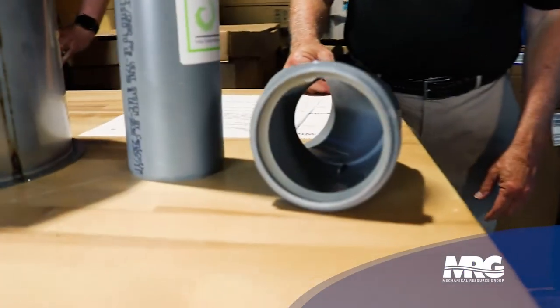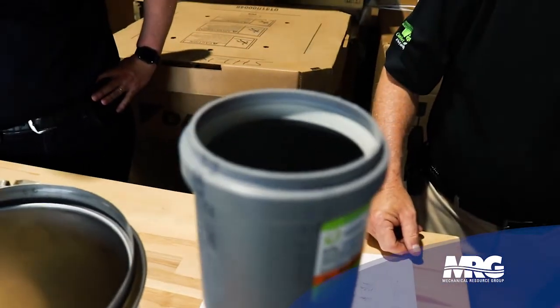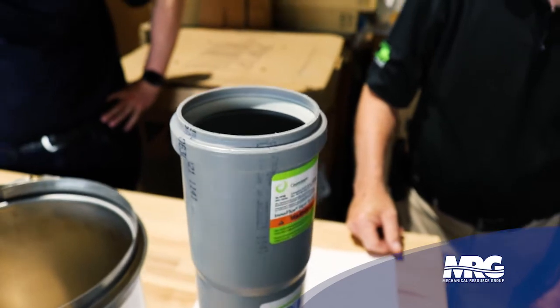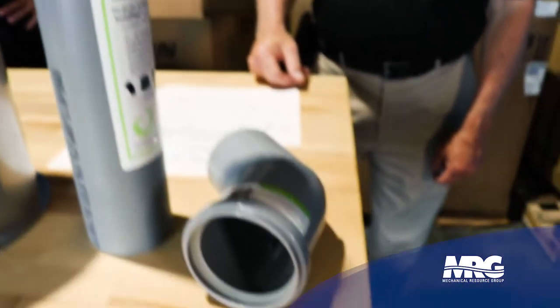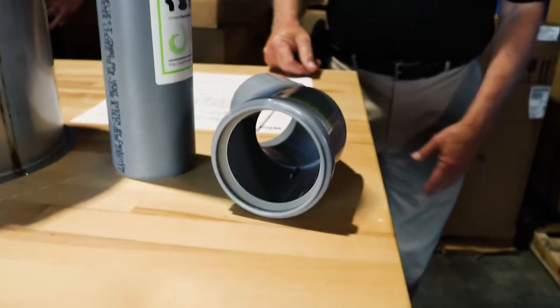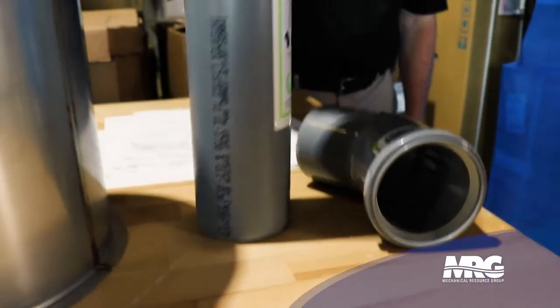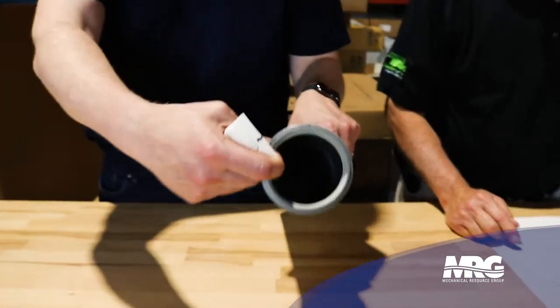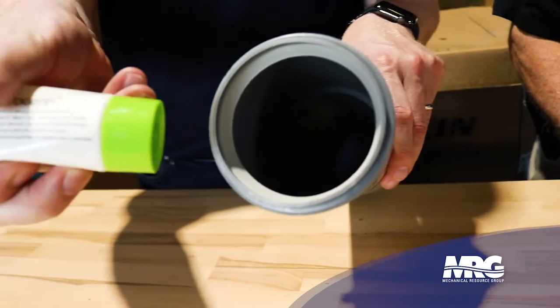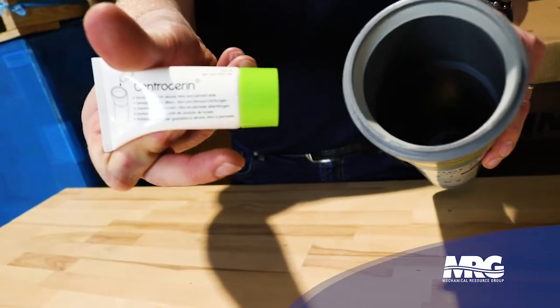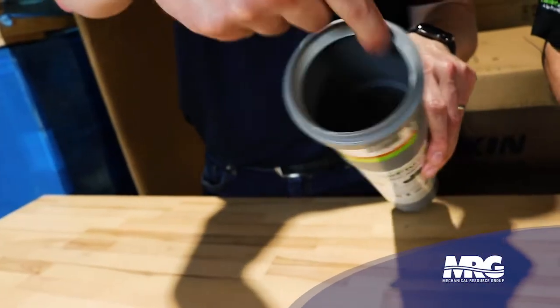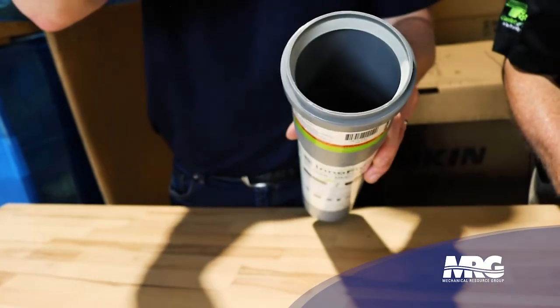We were talking about on the Category 4 material, which is a lot of the condensing boilers that we're using in the heating, and we're using the smaller ones, and that's where we can use this polypropylene pipe now. And that's the newest thing out on the market. It also has a rubber joint seal inside. It has a lubricant, can be cut. That's the beauty of this. It can be cut in the field, and it comes in several different lengths so that you don't have any waste, because if you do cut it, whatever you cut off is wasted.